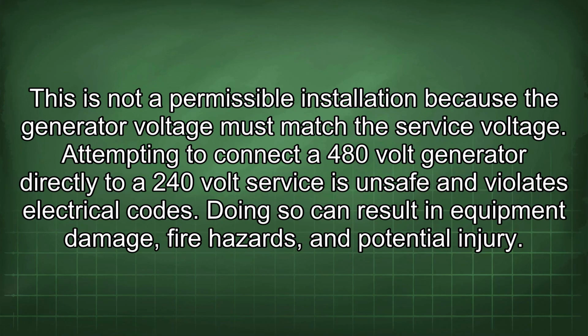This is not a permissible installation because the generator voltage must match the service voltage. Attempting to connect a 480-volt generator directly to a 240-volt service is unsafe and violates electrical codes. Doing so can result in equipment damage, fire hazards, and potential injury.